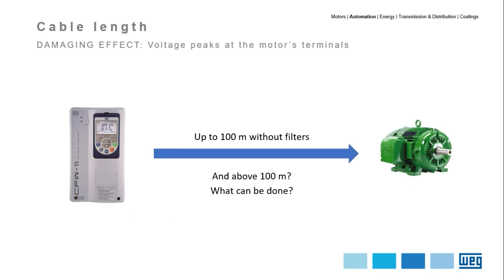Well, these applications may require special equipment called output filters, which are commonly installed inside the VSD panel and very close to the drive. So, the main function of this additional filtering equipment is to strip certain frequencies from the voltage waveform.